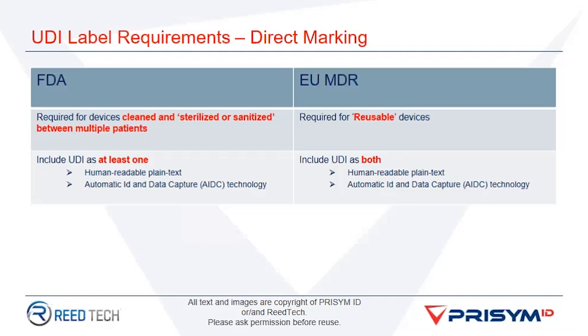For example, you might have a higher container that has a couple different expiration dates assembled together, so the question is which expiration date you use. The guideline has been to use the most current, or the one that would be enforced earliest. As you look at some of those production identifiers, that's probably where it comes into play.